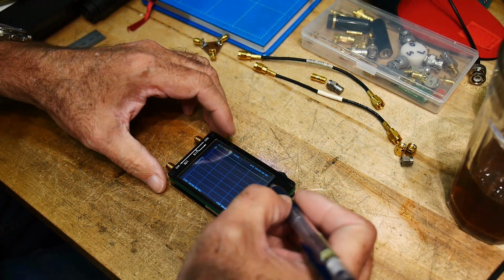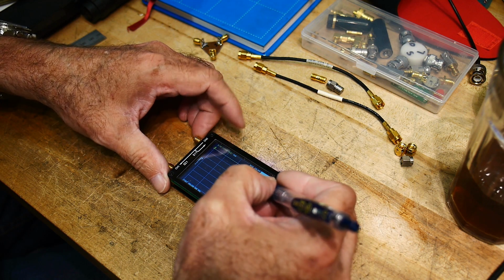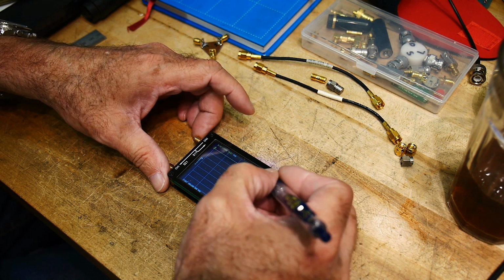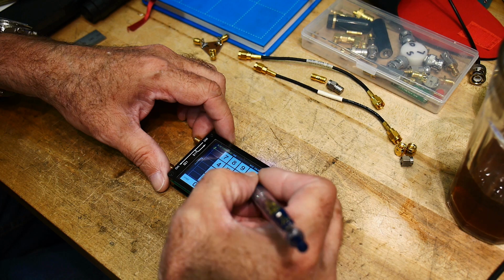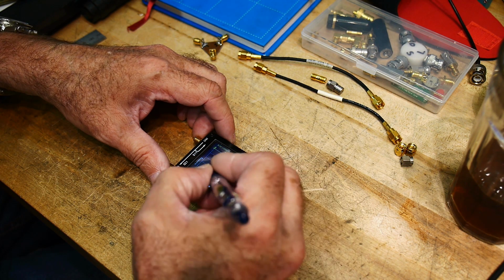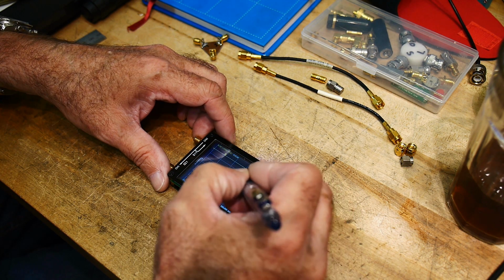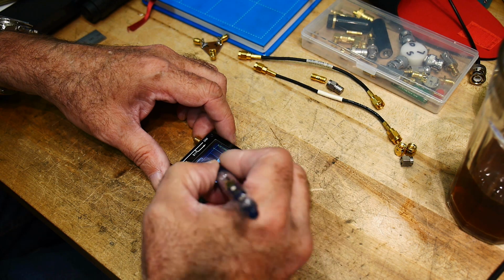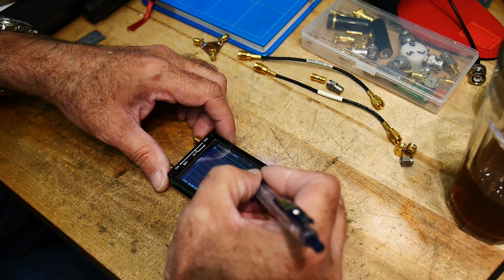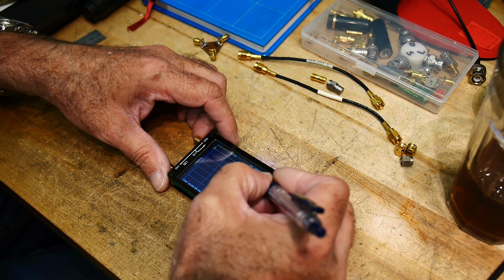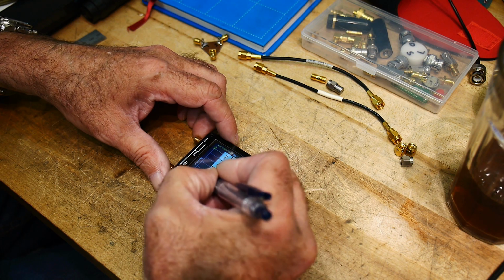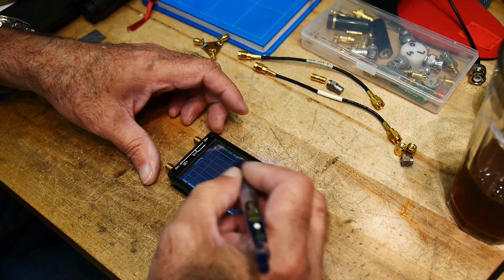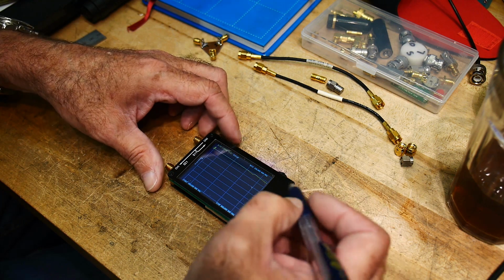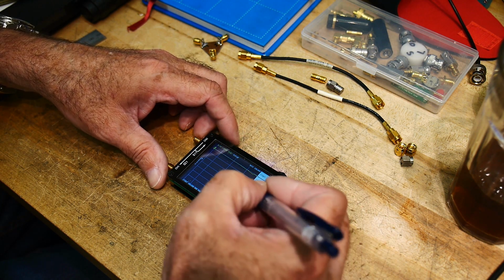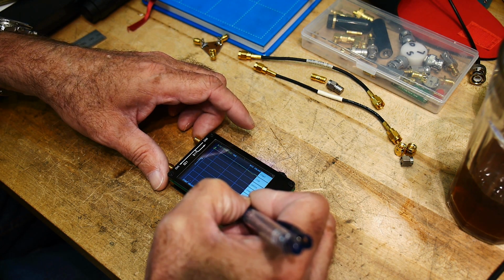Okay, let's set this thing up. Let's set it up to sweep between 100 megahertz and 900 megahertz. So we're going to sweep between 100 and 900. And now we're going to have to do a fancy calibration.